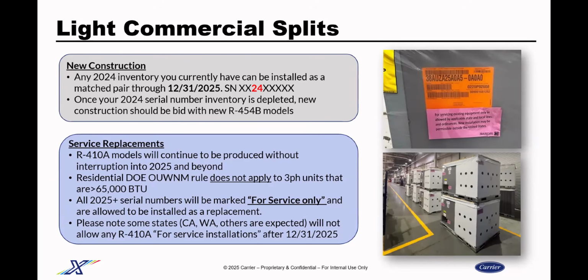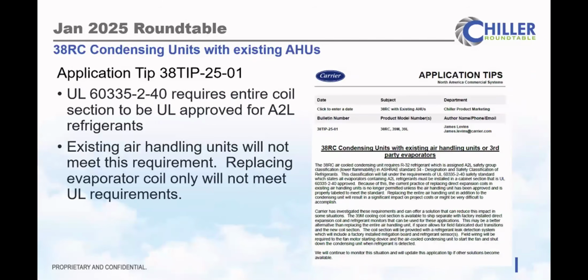For air handlers, it's already over. For fan coils, it's already over. They can't make any of that stuff. But evaporator coils, they can. I suppose the idea probably is, hey, if somebody has a 410A failed evaporator coil under warranty, it's significantly easier just to swap the whole coil than it is to keep the coil cabinet and just pull the guts out and swap that. So that's probably why they're doing it that way.